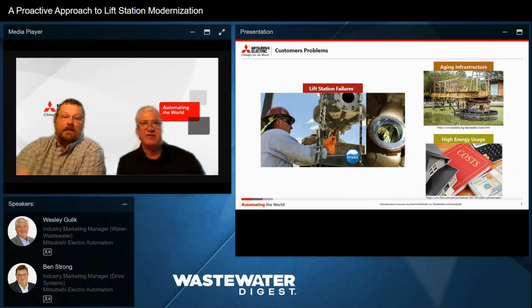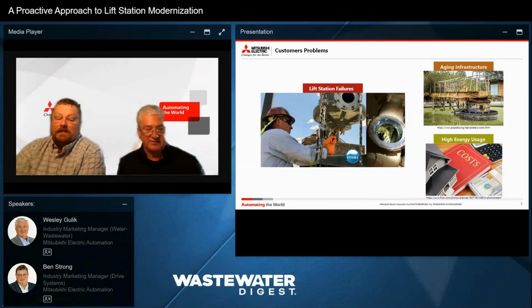So the three that we are going to be covering primarily in this session is the lift station failures. So over there we have a picture shot. In this case, it was a critical failure. That pump, as you can see, is being lifted from the well. As you can see, it could be wipes, it could be multiple different things that are stuck in that lift station that are being removed. And we did notice a huge spike, especially during COVID, 3-4 years ago. Those flushable wipes, not so flushable, and those were being found in these lift station pumps and creating all kinds of havoc and problems.